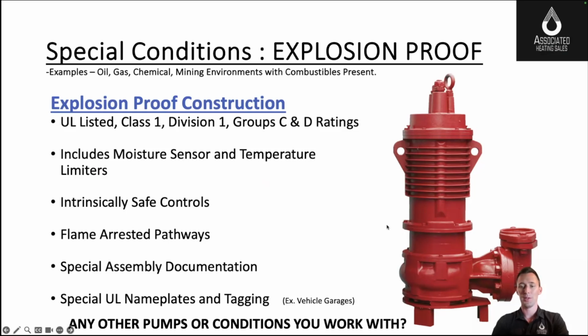It's also coupled with intrinsically safe controls, so low voltage, intrinsically safe relays within the panel to floats that run on low voltage. Typically, there are gold-plated contacts within those floats to allow for controls to operate, and again, to not allow any sort of sparking to occur outside the floats.